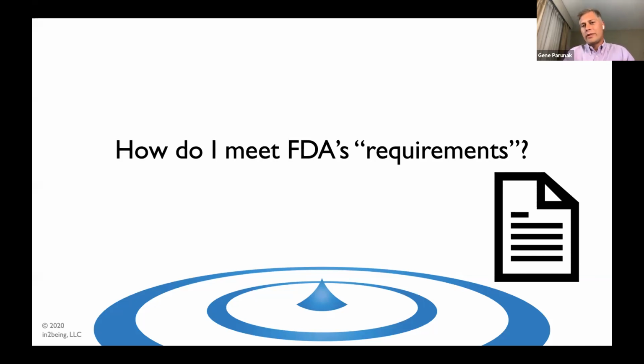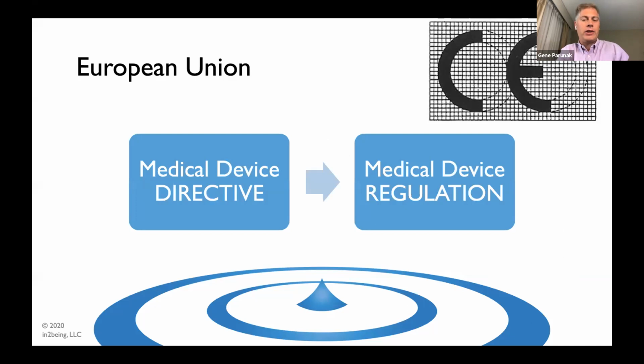There's some truth to that, but it's not the whole story. In fact, up until recently, that was kind of how things worked in the European Union. That's an oversimplification, but under the medical device directive, which is outgoing right now, going into the medical device regulation, devices were often authorized on the basis of standards compliance. You find the standard that applies to your device, you meet it, you get your compliance blessed by the notified body working on behalf of the government. That's changing as we move to the medical device regulation in Europe.